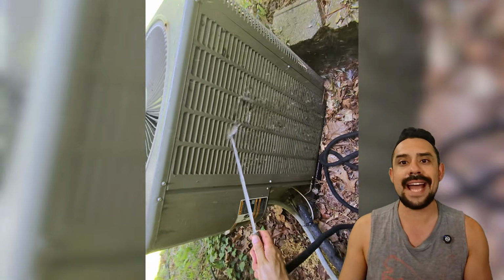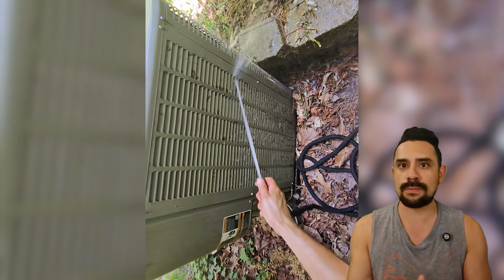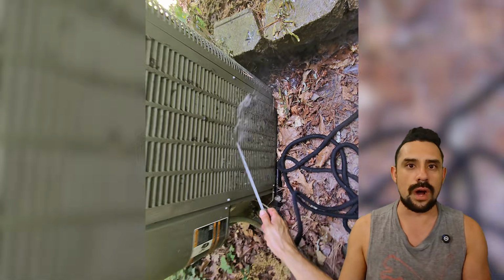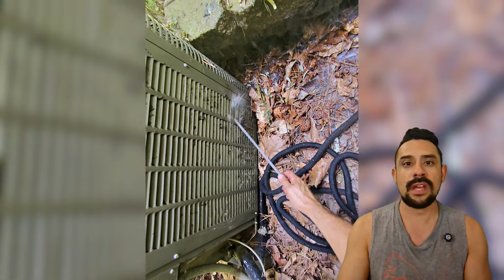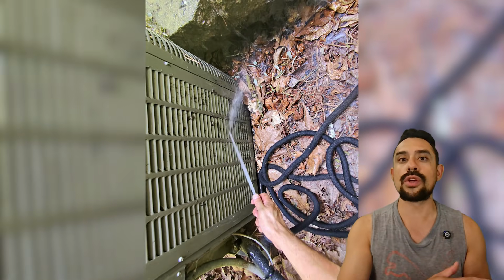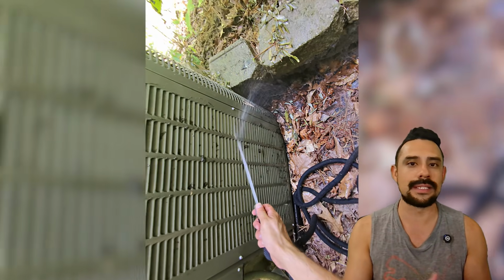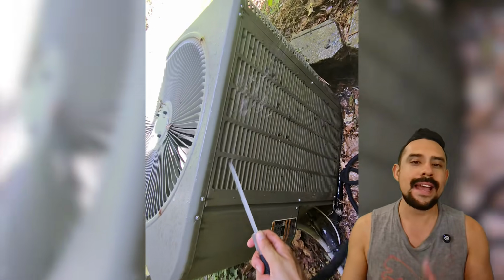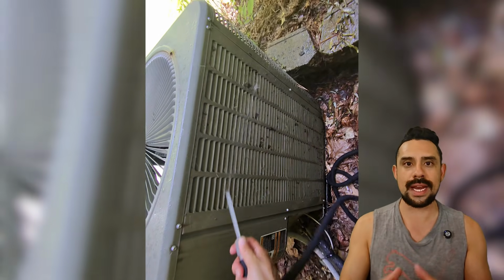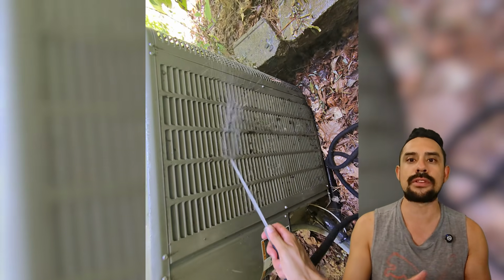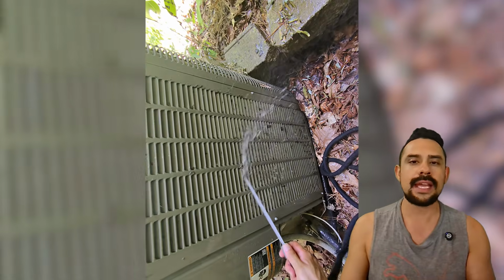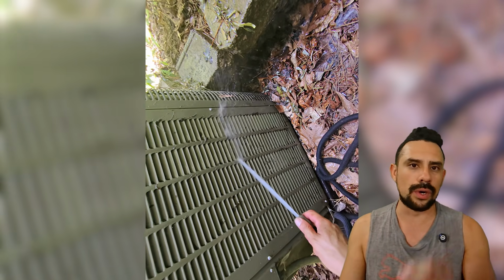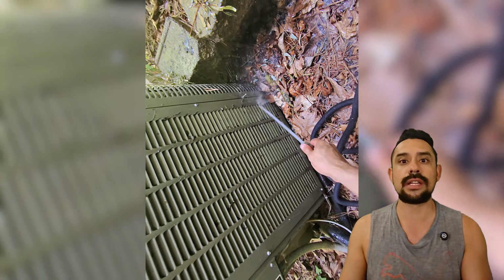When you hose it down, use a gentle to medium spray. You don't want a heavy pressure washer, as that can damage the fins. Start at the top of the unit and work your way down in slow, even side-to-side strokes. Make sure to spray the water straight into the fins so it can push the trapped dirt back out the way it came.